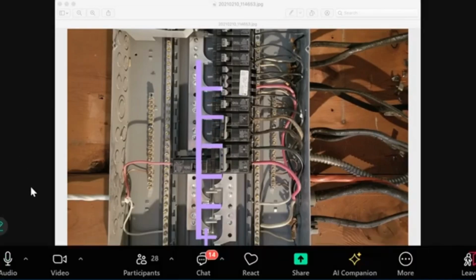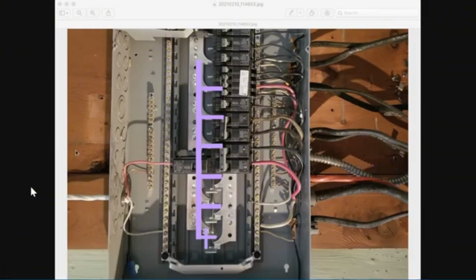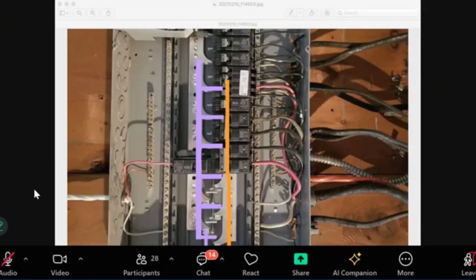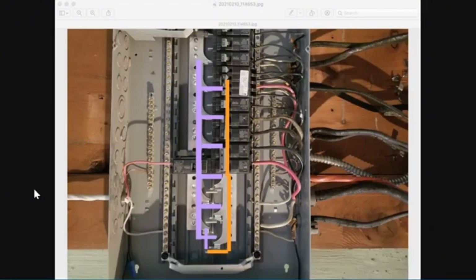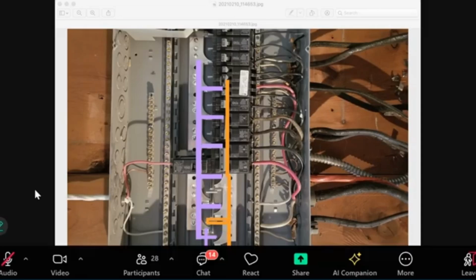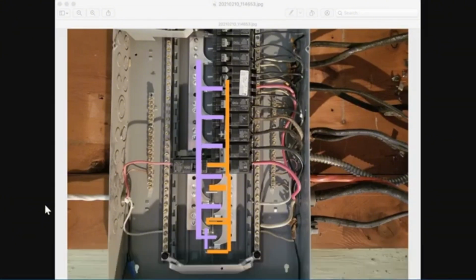So no, they're not connected to each other—that's this bar, and here's the other bar, which is behind these breakers too. You can see this blade coming out here, and they're not touching each other—they're intertwining. Every other one: behind this breaker there's a blade here, and behind this breaker you can see the tip sticking out right there. Now they interlock with each other.